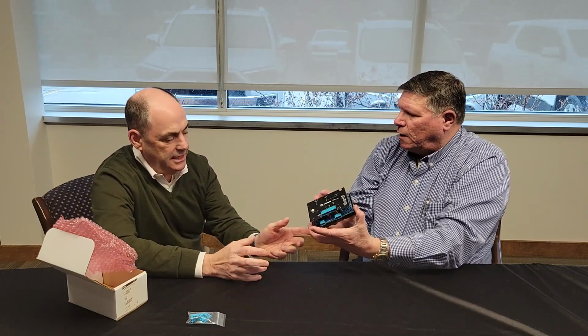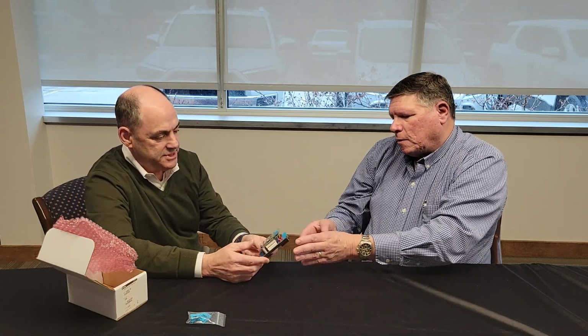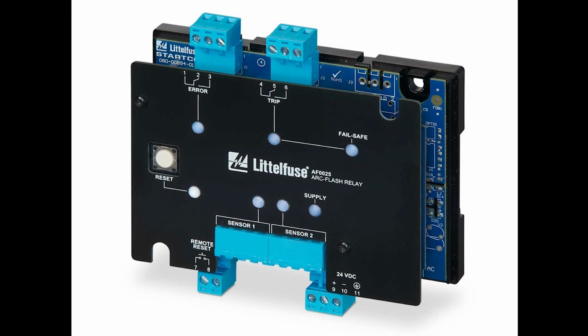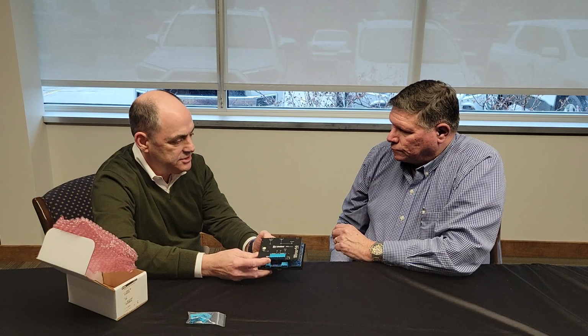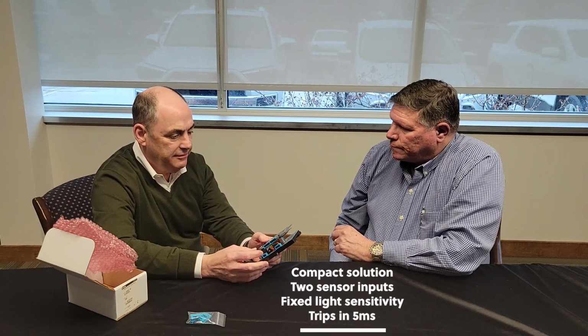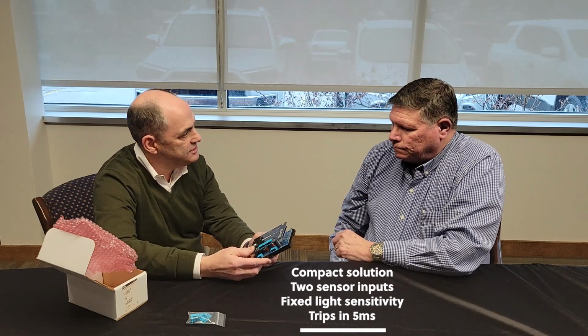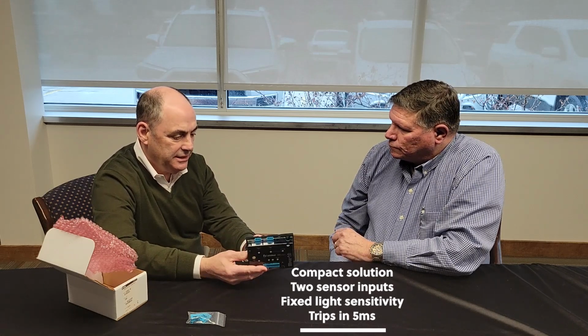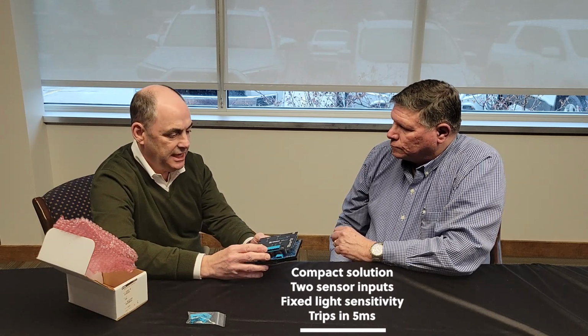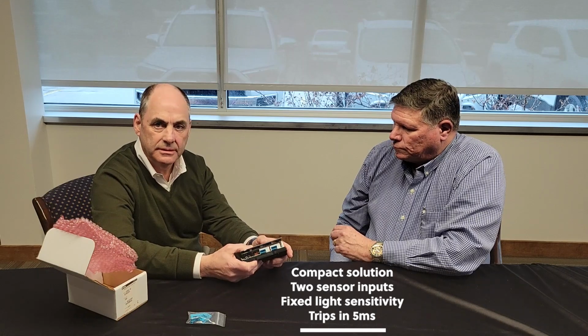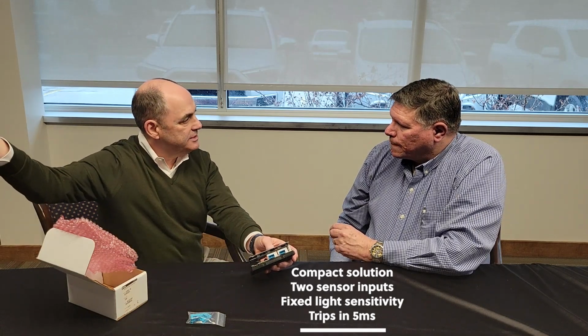So does it use the fiber optic detection as well? No, it does not. So this particular relay is built primarily for OEM applications. So it's lower cost than the other three Arc Flash relays. And it was designed primarily for OEMs and smaller cabinets where they require Arc Flash. Functionally, it does all the same stuff, uses the same technology that we use in the bigger ones. It's just got less inputs. This one has 2 inputs. The bigger ones might have 4 to 8 inputs in it.